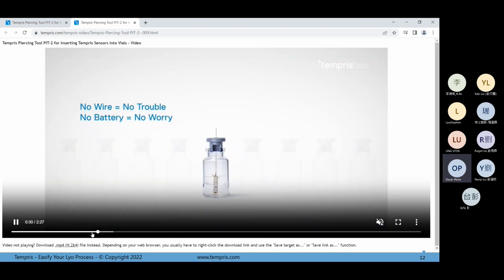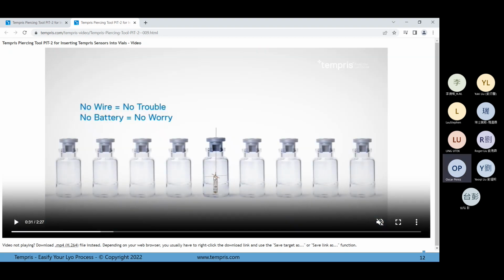And let me go back. It's faster than me. Center crosspiece is specific. The only difference is the length of these arms that we can see, in order to keep the sensor centered inside of the vial. So for bigger vials, of course, the center crosspiece will be longer. And it's made in PEEK material, so it's suitable to be sterilized and to be in contact with the product.